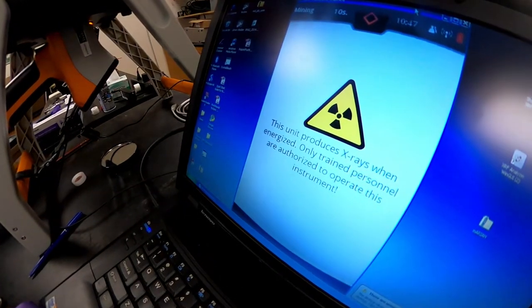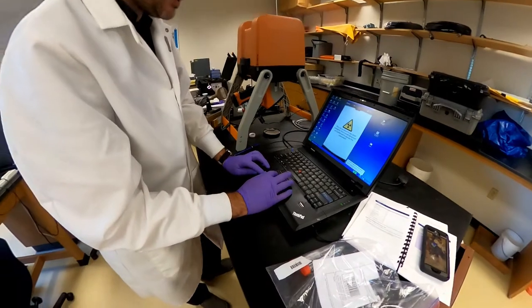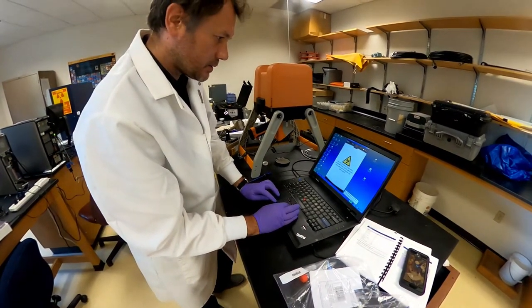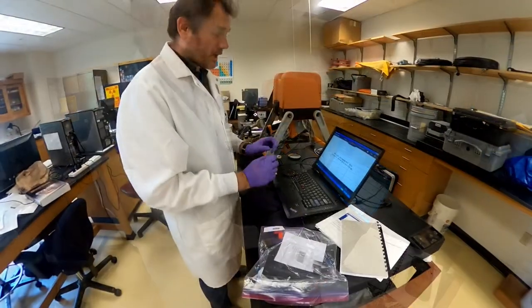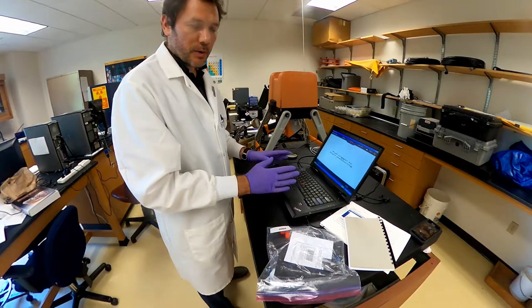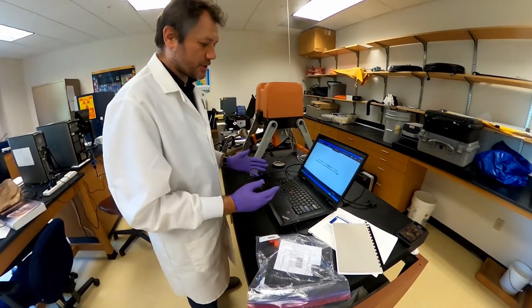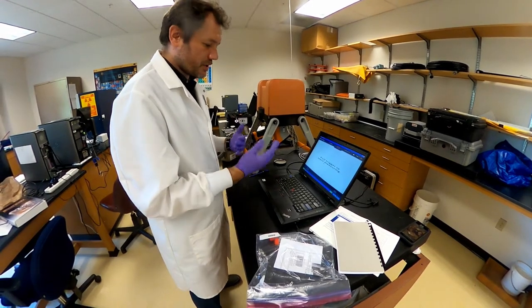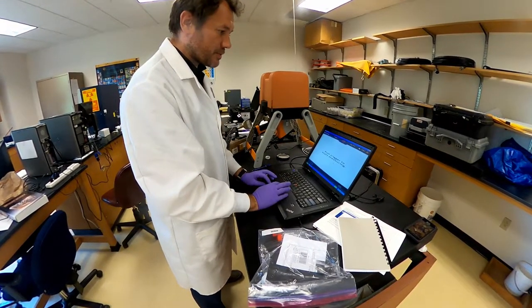And then I will turn on the X-ray and here we go. So, it tells us that of course this unit is producing X-rays, so we need to be careful. So, we can operate the X-ray via the computer or we could operate the X-ray independently. We'll do it through the computer. It's just easier and more comfortable.